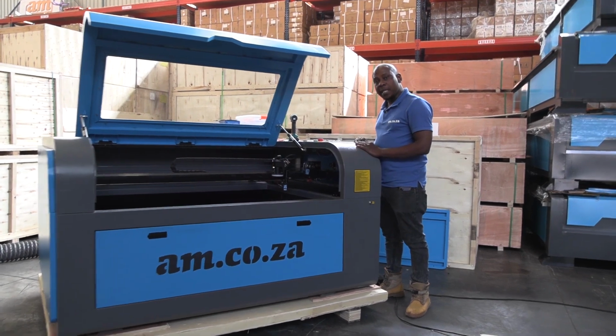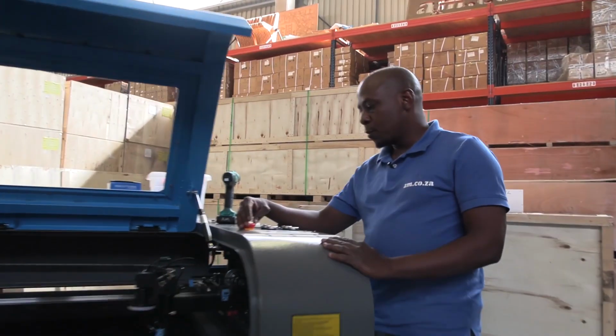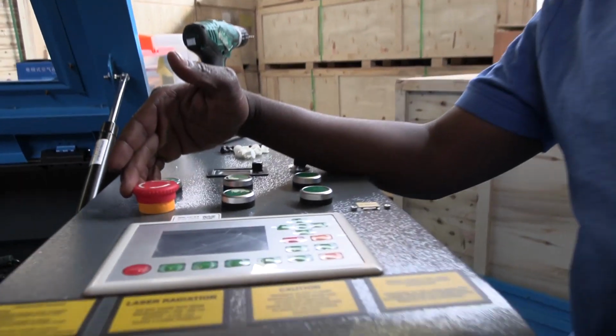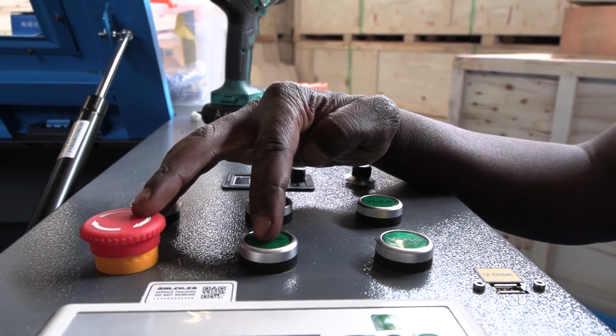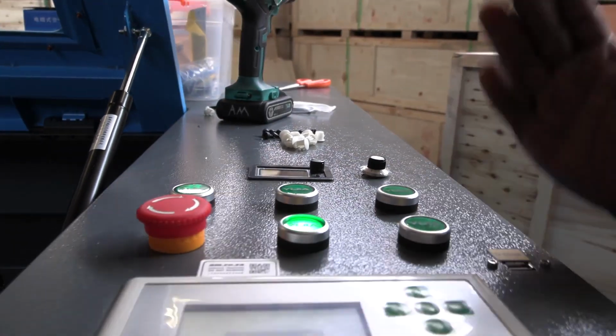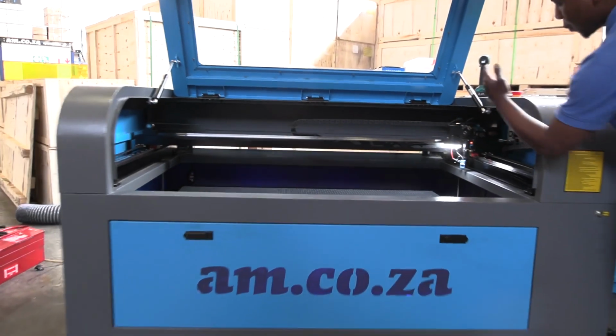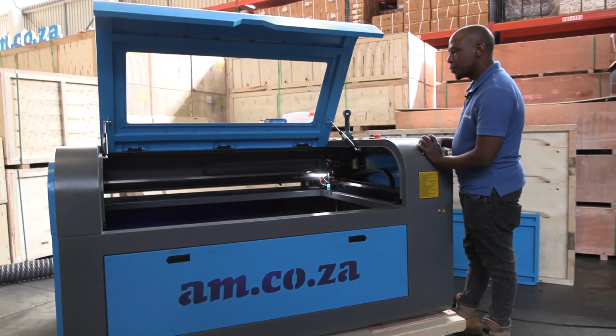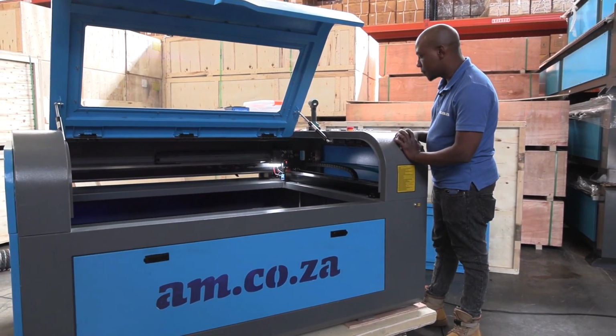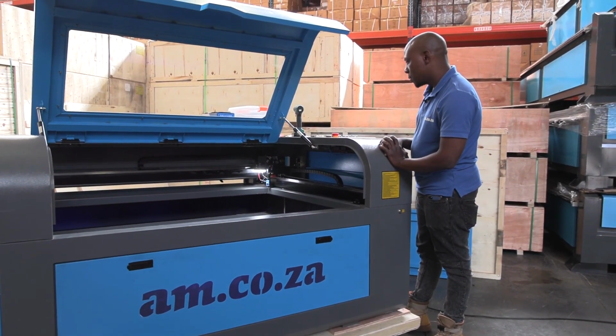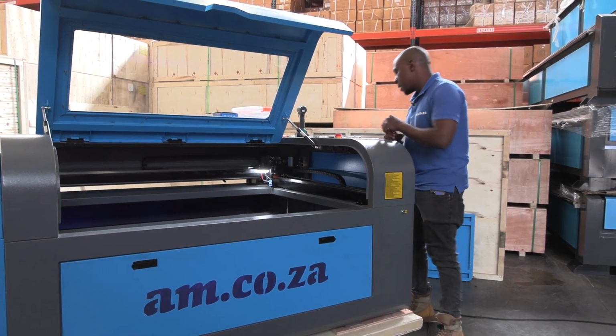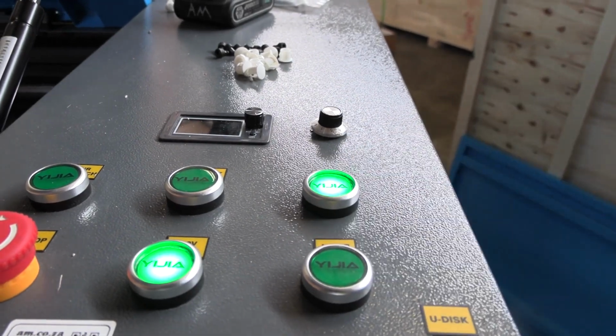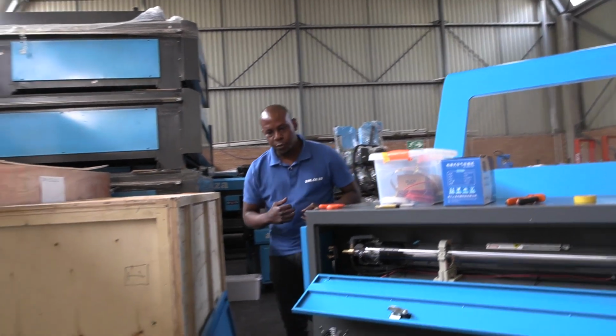Switching on is very easy. First, I would want to disengage my emergency stop switch and push down my 220 input switch. There goes the motherboard on. The machine is going to reset, going to its homing position. Once that is complete, I can switch on my chiller switch and proceed to switch on the chiller unit.